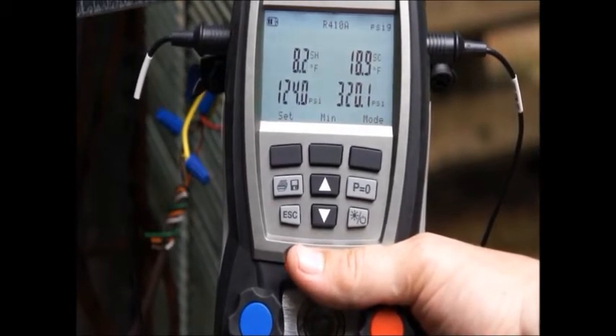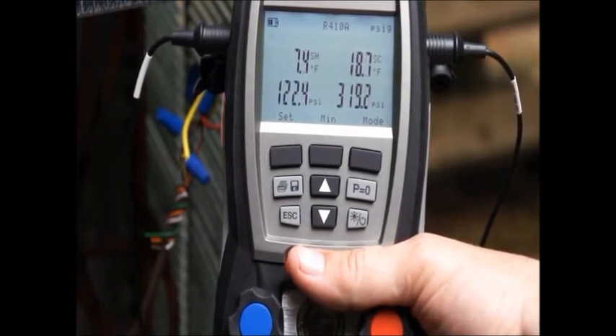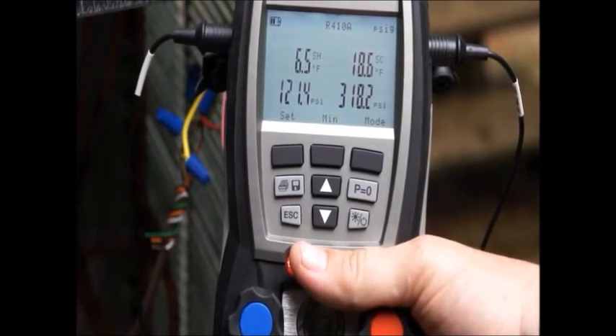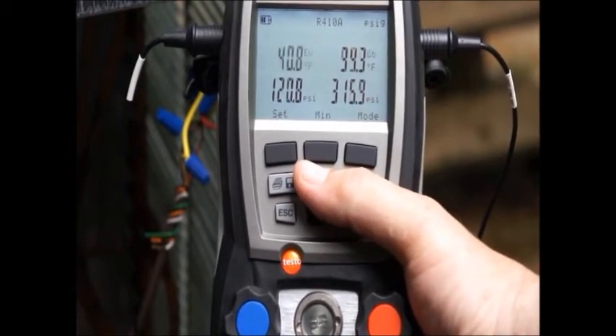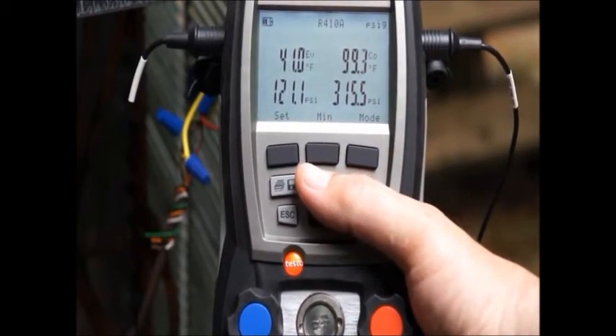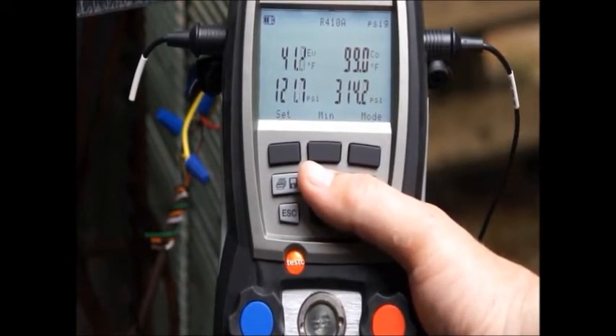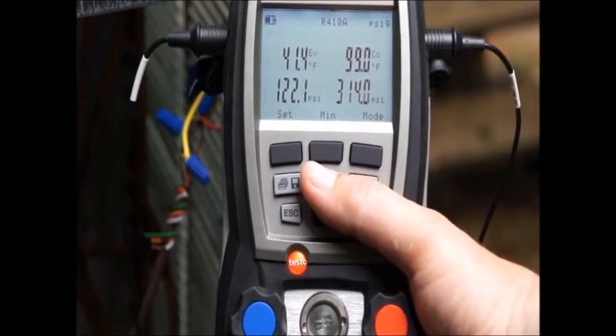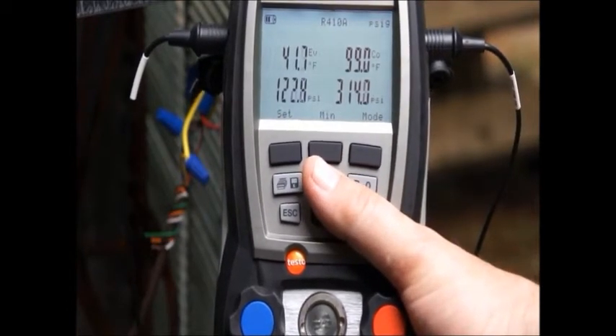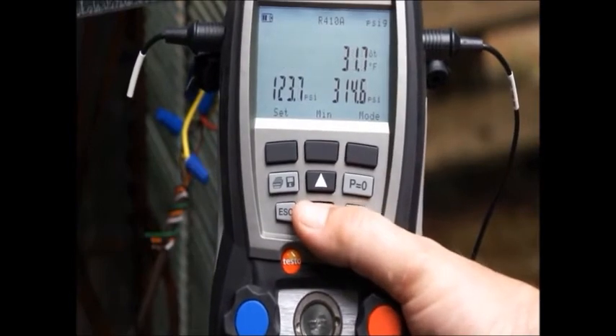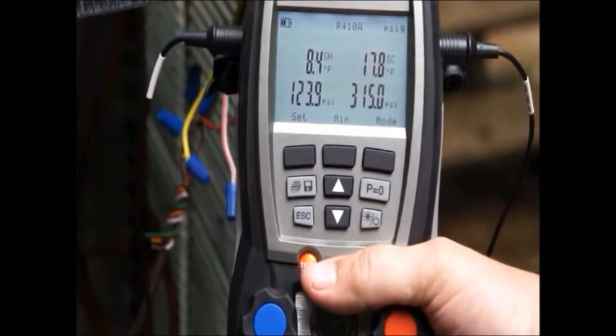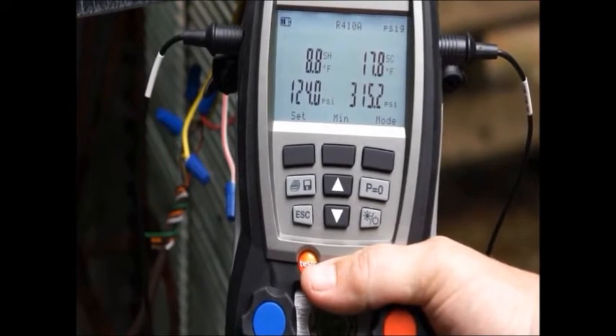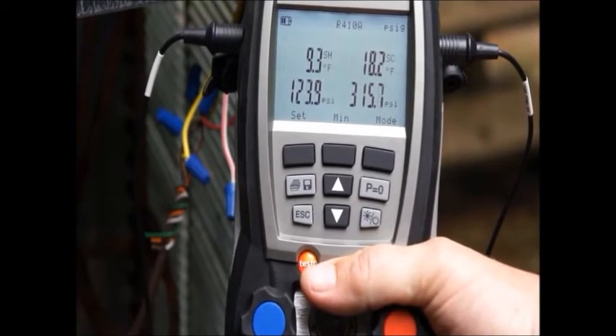We've got to give it a little bit of time to settle out. Let me look at my condensing temp - about 99 degree condensing temp and it's about 80 degrees outside. So we're a little bit higher just looking at general temperatures, obviously because we've got a plugged up condenser. But one thing to note is even though that condenser is plugged up, it's not going to affect the subcooling reading because we're just going to get the same subcooling at a higher condensing temperature.